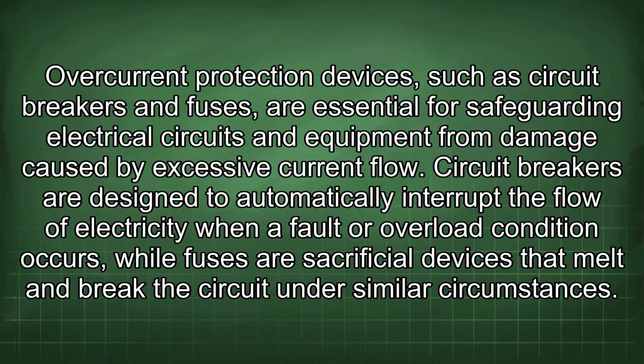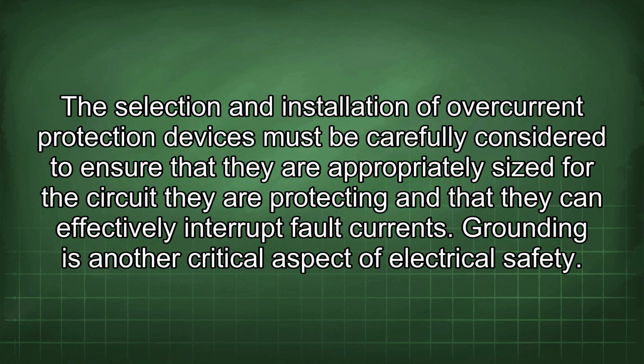Overcurrent protection devices, such as circuit breakers and fuses, are essential for safeguarding electrical circuits and equipment from damage caused by excessive current flow. Circuit breakers are designed to automatically interrupt the flow of electricity when a fault or overload condition occurs, while fuses are sacrificial devices that melt and break the circuit under similar circumstances. The selection and installation of overcurrent protection devices must be carefully considered to ensure that they are appropriately sized for the circuit they are protecting and that they can effectively interrupt fault currents.